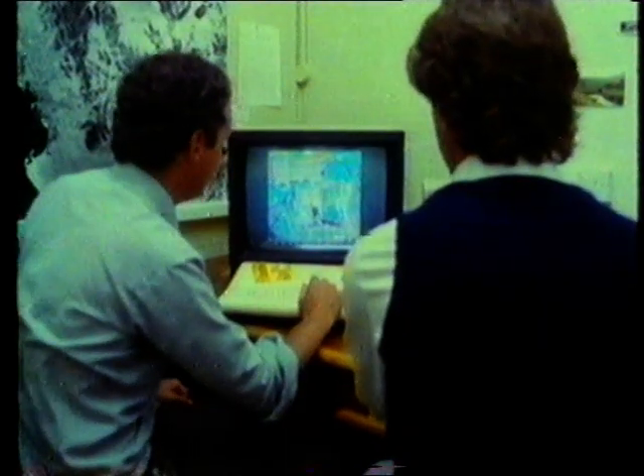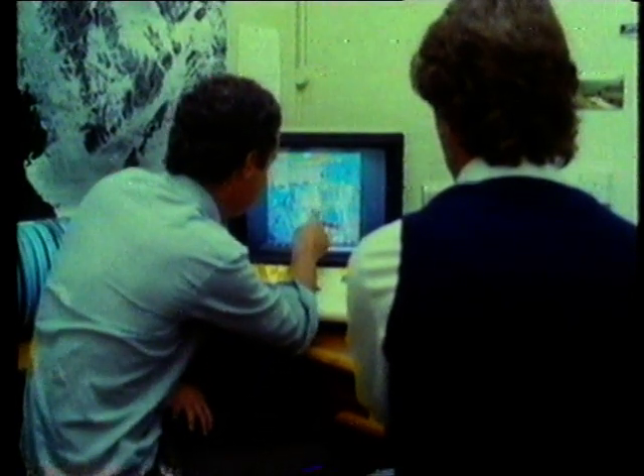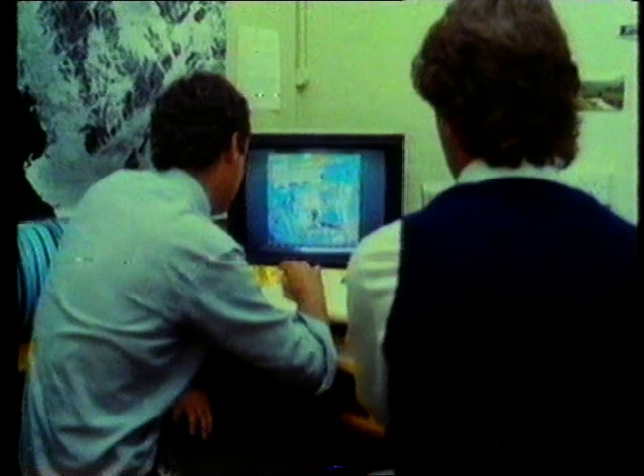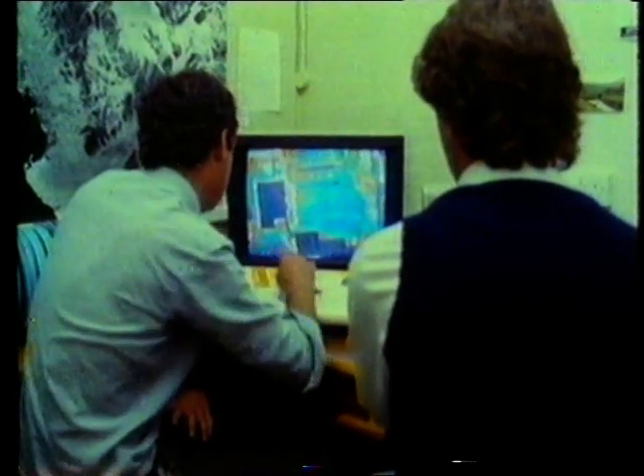What do you learn from looking at an image like this? Yes, we can see an obvious area here of white heat loss, which we can zoom in on. You can see the white underground pipe here, which is obviously losing heat, which is hotter than the surrounding areas.